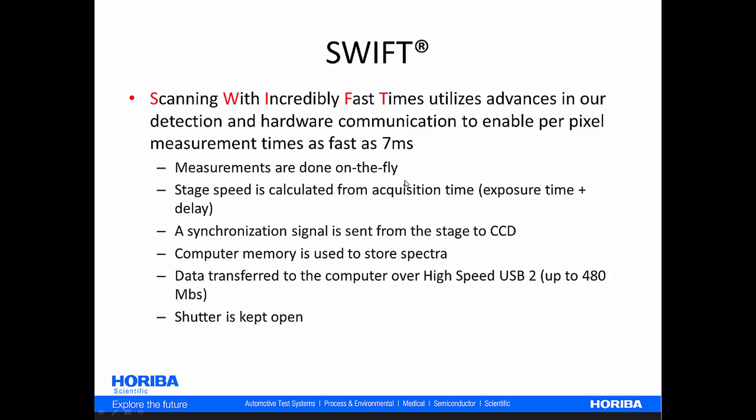So what we have then are measurements that are done on the fly. This stage is continuously moving. And the stage speed is calculated from the acquisition time that's set. So it's controlled by the camera. And you have a synchronization signal sent from the stage to the CCD. And computer memory is used to store the spectra. And the data are transferred over high speed USB connection. And the shutter is kept open throughout the entirety of the data acquisition.